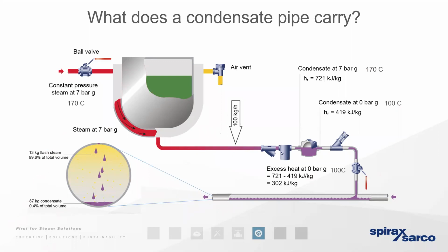And that's what catches a lot of steam using sites out, because the best way to deal with that expansion of volume, so they believe, is to vent it away to atmosphere. Once we've vented that expansion away to atmosphere, we can now pump the condensate back as a liquid all the way back to the boiler house. And if we're pumping it back as a liquid, we're not at risk of cavitation, and we're not at risk of having to do so in a very large size pipe diameter. Because if we're pumping a liquid, that flash steam's gone. And yes, that certainly is the case. But by losing that flash steam, we're losing a significant amount of energy that could potentially be used elsewhere.